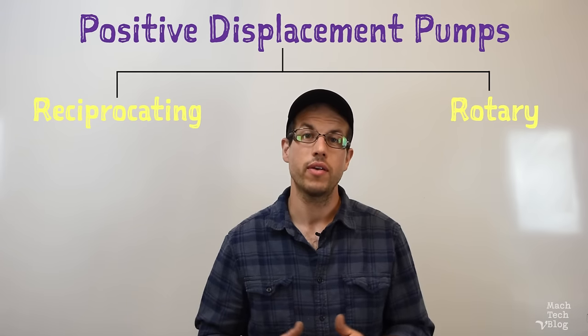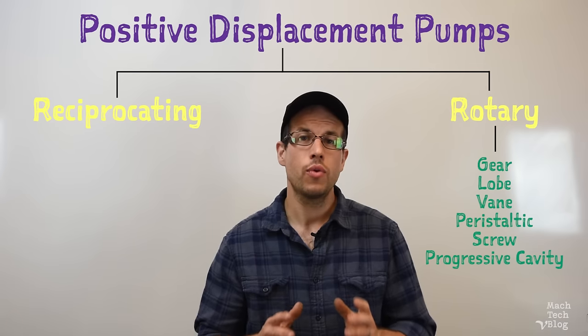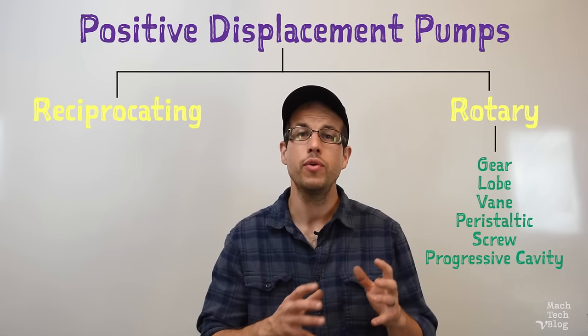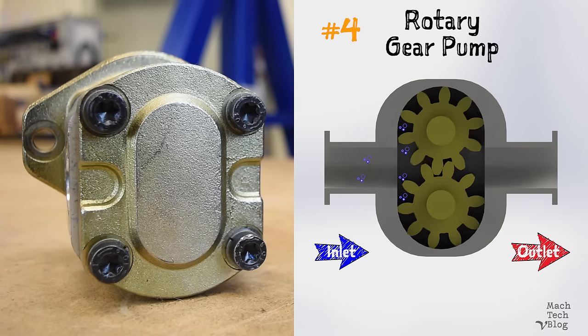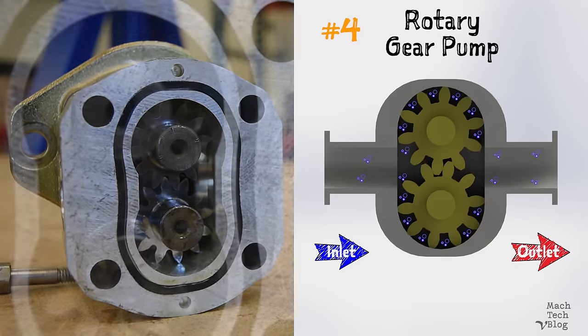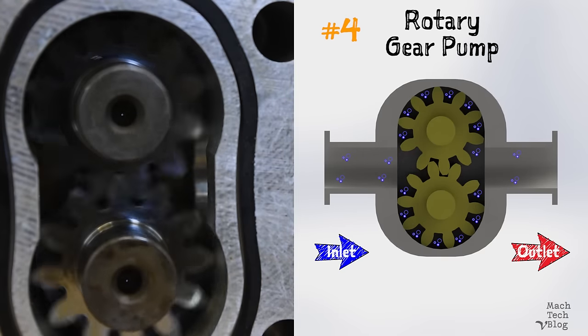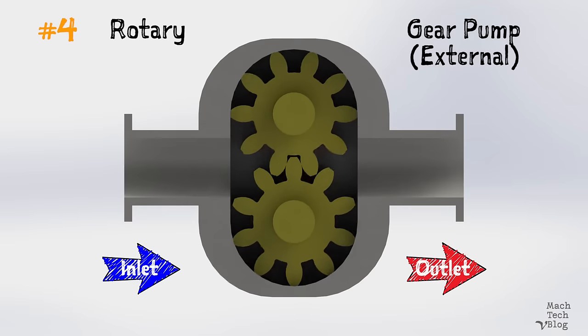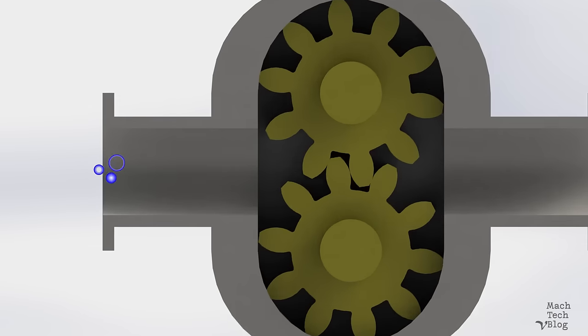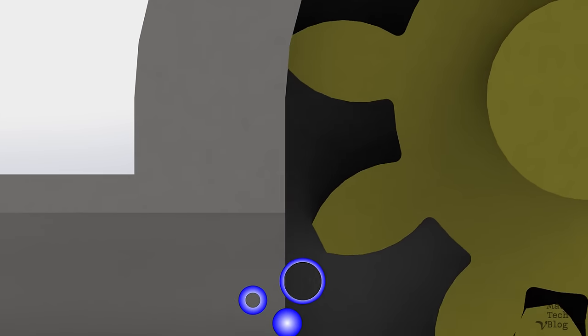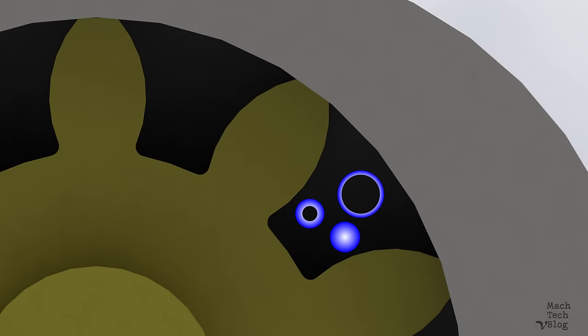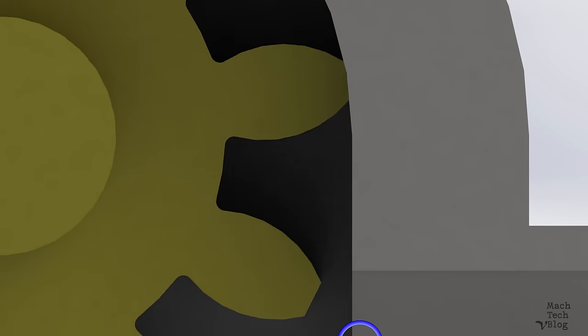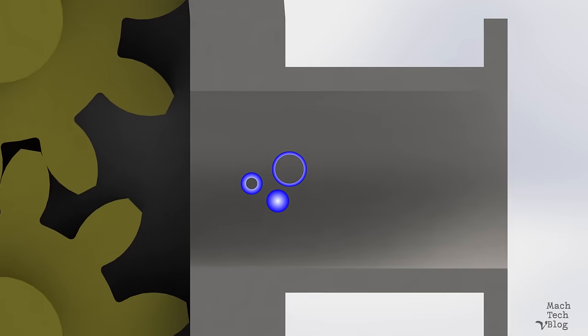The second category of positive displacement pump is the rotary pump. All rotary pumps utilize some kind of a moving chamber that traps fluid and carries it from one side of the pump to the other side. To illustrate this concept, let's look at pump number four: the gear pump. This configuration is more properly called an external gear pump. The mechanism consists of two rotating gears, one driving the other inside of an oval housing. At the suction inlet, fluid is trapped in a chamber between the gear teeth and the inside wall of the housing. The rotary motion moves the chamber from one side of the housing to the other, and as the gear teeth rotate back into mesh, the chamber is closed, forcing the fluid through the discharge outlet.